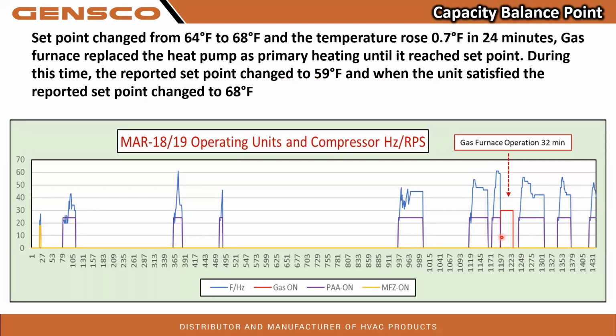So when it's running the gas furnace, one thing it's going to do is stop looking at actual return temperatures, and it's going to assume temperatures until the thermostat tells it otherwise. But you'll see in here that once it hits its set point, it goes back, switches the furnace off, and goes back to running normal cooling or normal heat pump mode again.